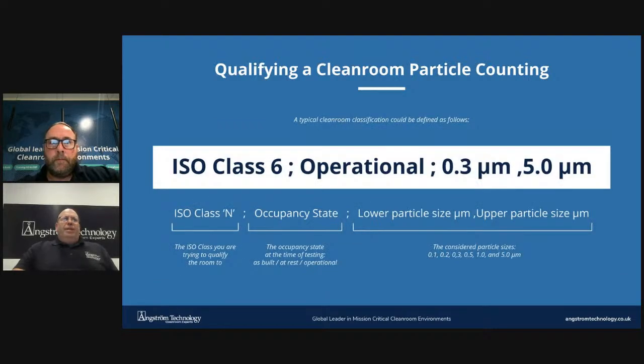So the clean room can be defined as follows. The ISO class we are qualifying the room to, and the 3 occupancy states, which are as built, at rest, and operational. As built, the clean room has never been used. It is brand new and probably the cleanest it will ever be. At rest, people have used the clean room and completed intended works, but they are not present in the rooms during testing taking place. It is not as clean as brand new, but it is cleaner than when the room is occupied with people moving around.